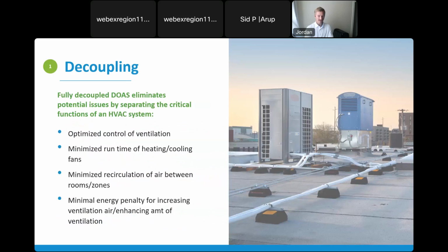Our experience is that that's actually a pretty small reason to do it. Even more impactful is having a lot of flexibility to ramp ventilation air up, to do flushes of indoor air quality before or after occupancy, and to optimize control of each space, not just to be able to shut them off, but to dial in each system to control to the function that it's designed for.